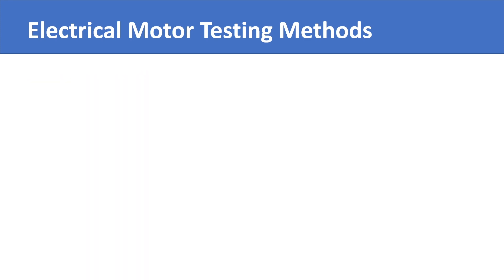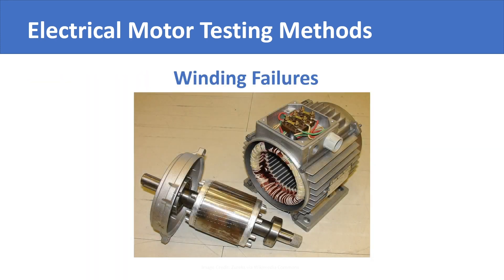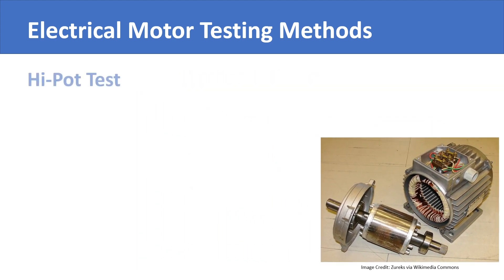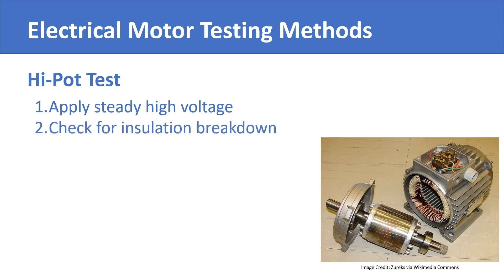One of the common failures of an electric motor is failure of its windings. There are multiple tests for detecting winding issues. A famous test is the high potential surge test, simply referred to as the high pot test. It involves applying a steady high voltage for a specific duration and checking for insulation breakdown and leakage current in the motor. Its purpose is to check the ability of the motor not to break down under high voltage spikes.